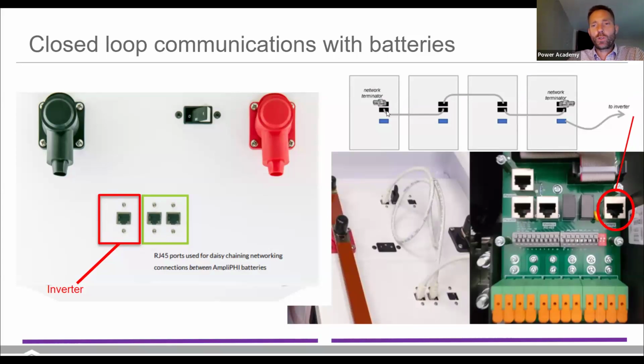So we go from the first battery to the second battery to the third battery to the fourth battery. Notice that the first battery and the last battery would have open ports, so we'll put a terminating resistor there, and that tells the CAN bus system that this is the last battery or the first battery in the chain. And then you can pull out of any of the batteries. It could pull out of the last battery and go to the inverter. So you need one of the batteries connected to the inverter through the device port, and that would make that connection here on the comms board inside the Sol-Ark 15K.